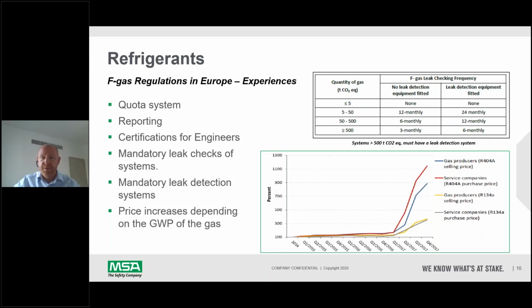They also had reporting for the usage of gas on site. Engineers had to be certified to use these gases, and then there were mandatory leak checks required for each system over a certain volume. And then for large systems, leak detection must be fitted. If you had leak detection installed, you can see in this diagram here, it actually reduced the number of leak tests you needed to do. So there were benefits to having a leak detection system installed. You can see here that the prices of the gas also increased dramatically depending on the GWP of the gas. So R404A had a much higher GWP than R134A, so the gas price increased much more.